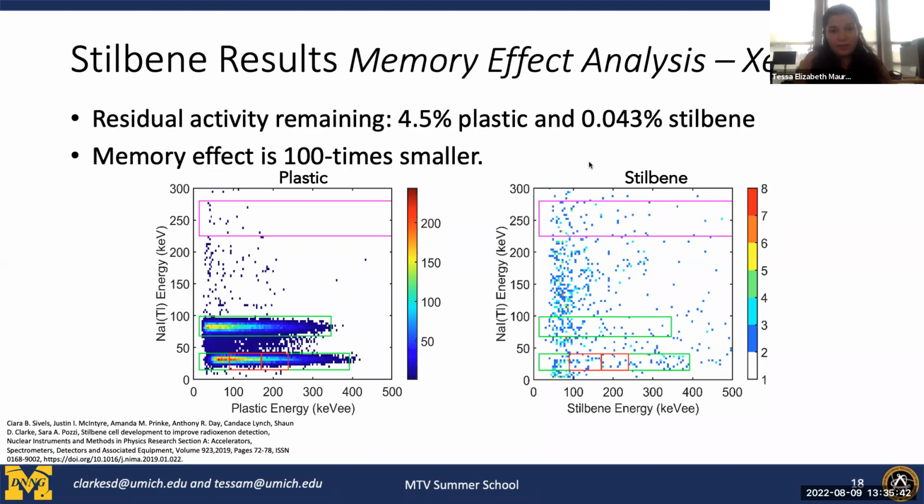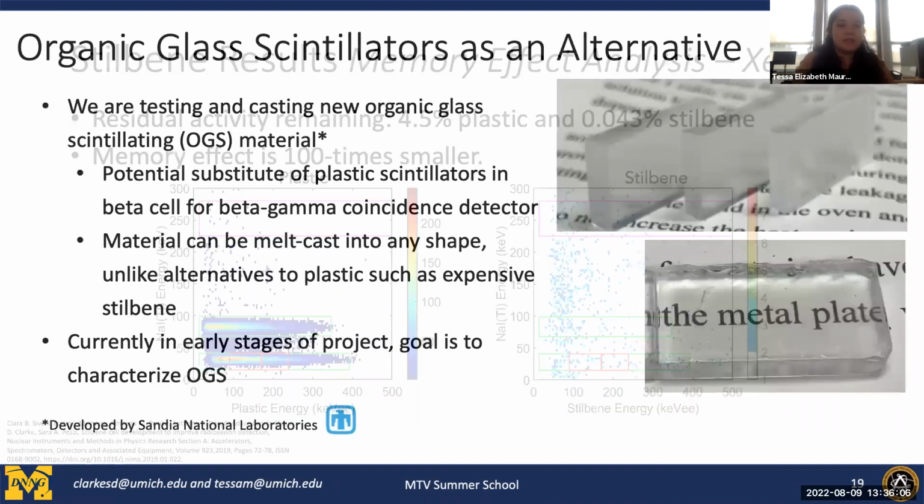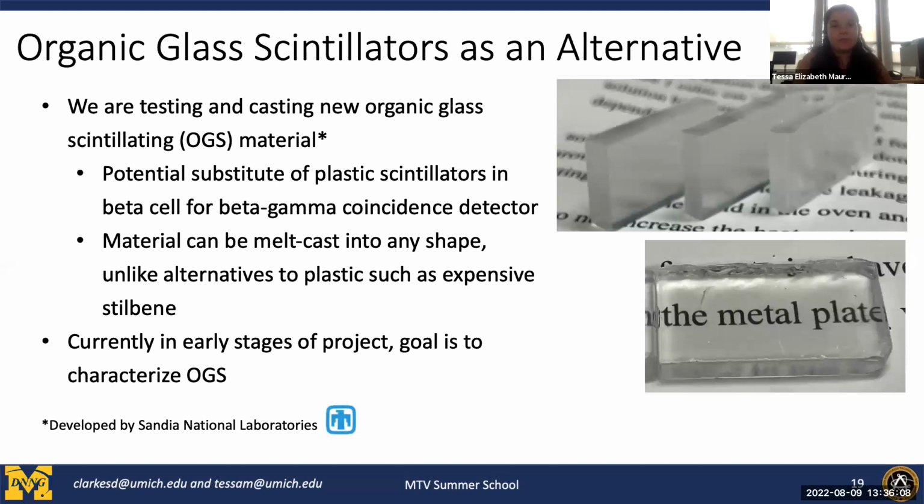In comparison, if you look at the stilbene on the right, we see a much reduced memory effect. It's actually 100 times smaller. So this was really encouraging, and stilbene has better energy resolution and reduced memory effect. So it looked like it could be a really good alternative to plastic scintillators, but stilbene is very expensive and not easy to shape. And that gets into my next slides here.